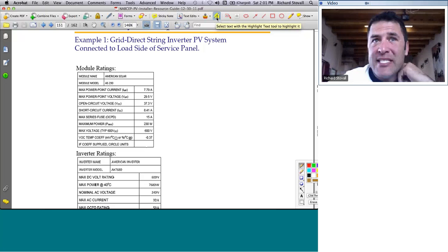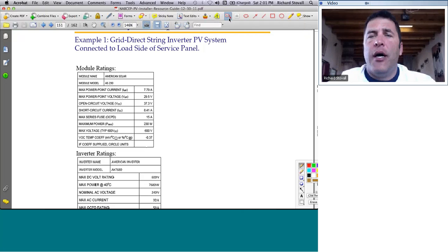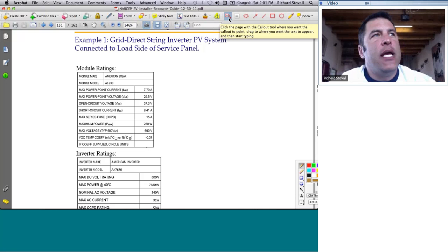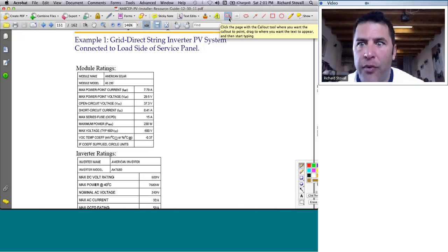In addition to that, Power One has this crazy voltage range. I don't know how they do it. They've got a transformer with the inverter, but they are able to operate in a voltage range as low as, I want to say 90 volts. It requires going in and doing some manual changes to their start voltage. But I believe it's a low of 90 volts and a high of like 550. It's like crazy high. So it's great flexibility. In the same way that the benefits of a microinverter allow you to have different modules in the system, Power One Aurora gives you that flexibility too.